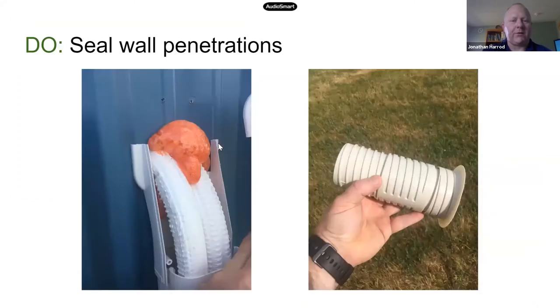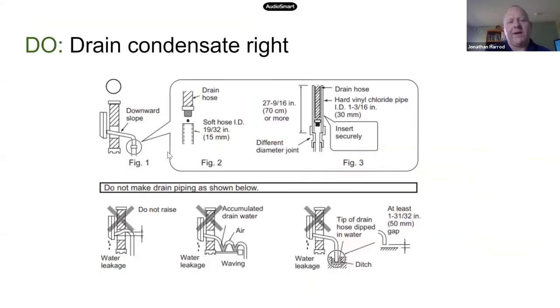So in order for that to work properly, we have to pay a lot of attention to the pitch of this condensate pipe, both where it leaves the house and all the way down to the ground. We have to make sure that it's sloping steadily, at least a quarter inch per foot all the way down. They do get filled up with algae and spider webs over time. And so we also need them to be accessible so that we can clean them out as part of our annual maintenance.